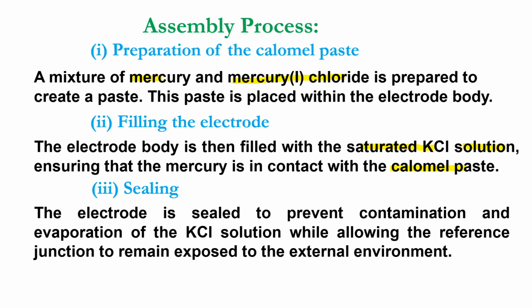Sealing. The electrode is sealed to prevent contamination and evaporation of the potassium chloride solution while allowing the reference junction to remain exposed to the external environment.